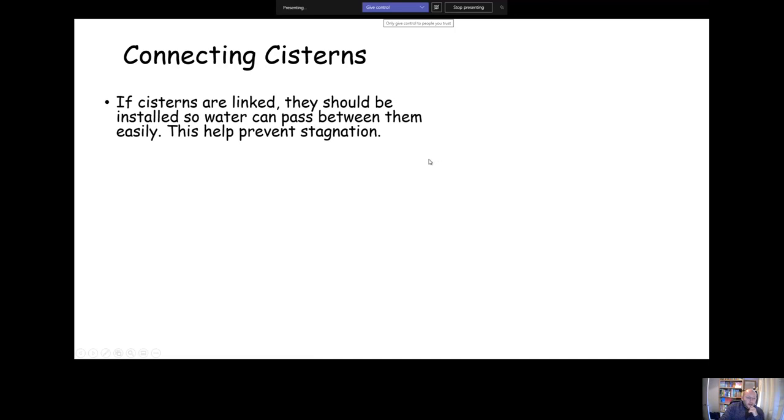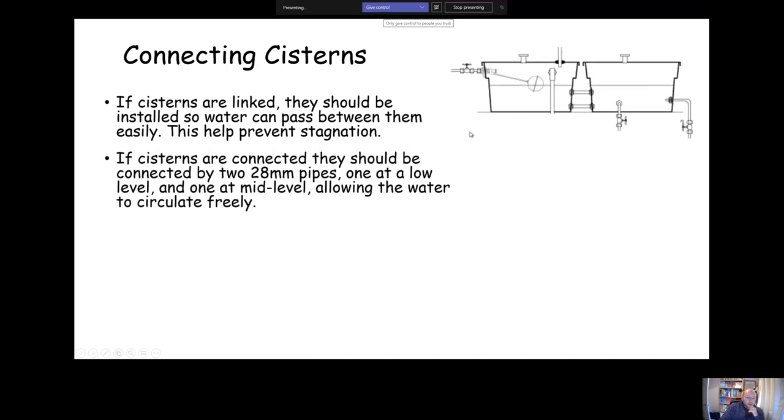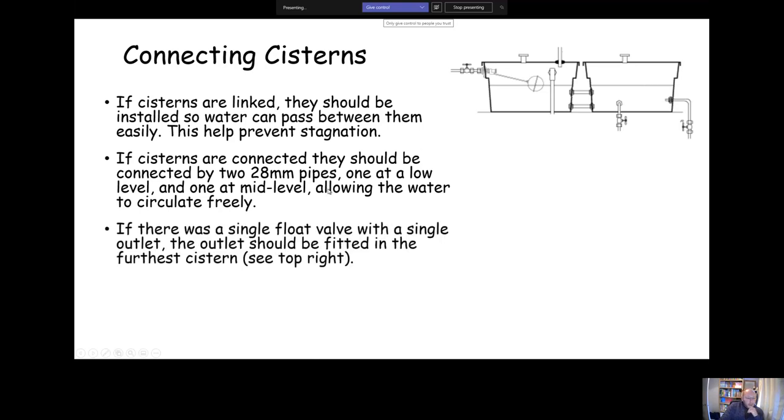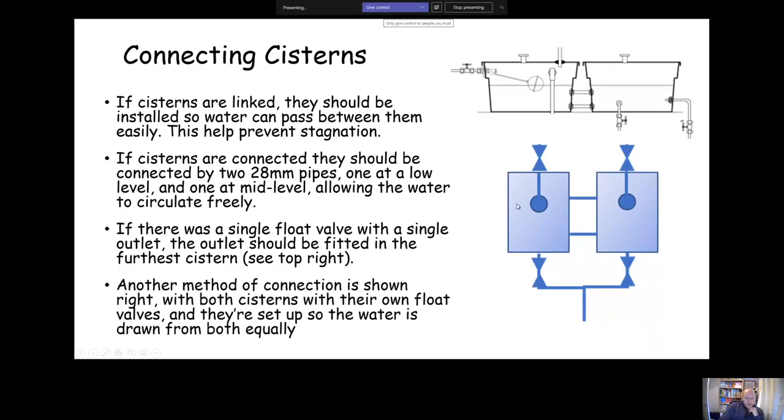So connecting cisterns: if cisterns are linked, they should be connected with two pipes, one at low level and one at sort of medium level. If you only have one inlet, you should make sure that the outlets are in the furthest cistern from the inlet. There's another method of connection here, you can see you've got two inlets and two outlets there. You want to try and make sure that you prevent stagnation, you get water flowing equally from both of them. If you have two float valves or if you have one float valve, you need to make sure that the oldest water gets used up first so it's not going to stagnate.